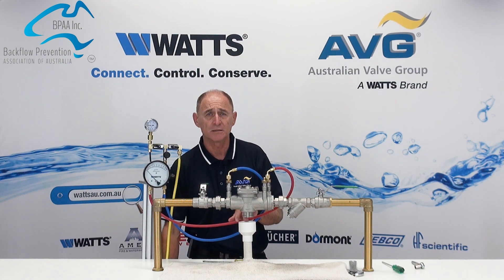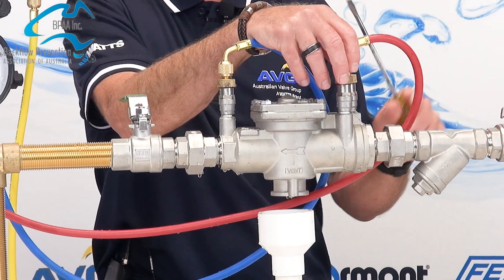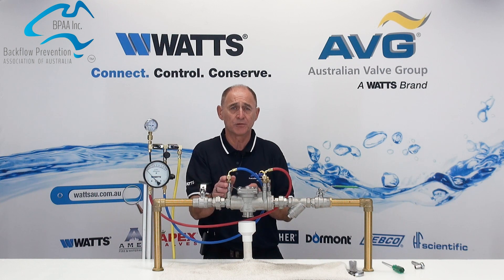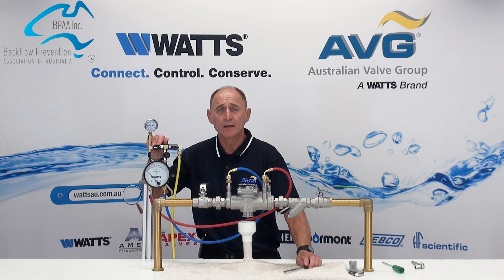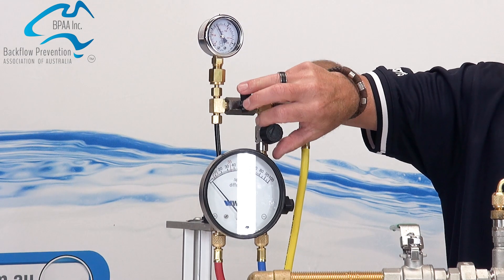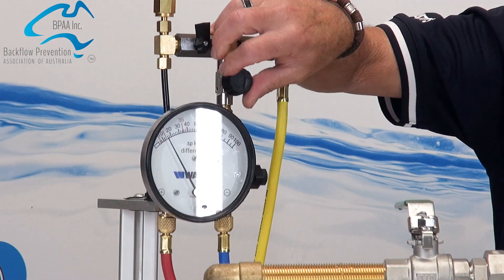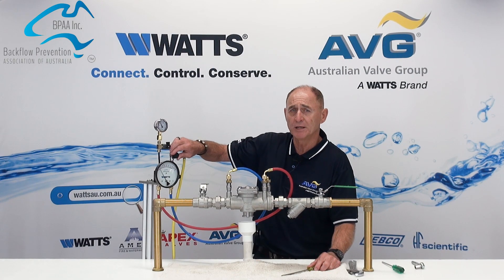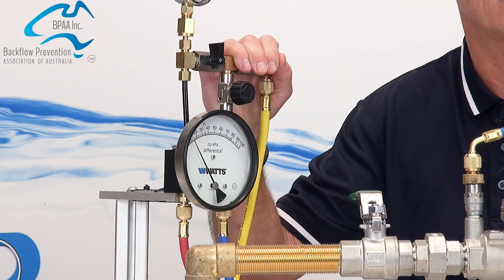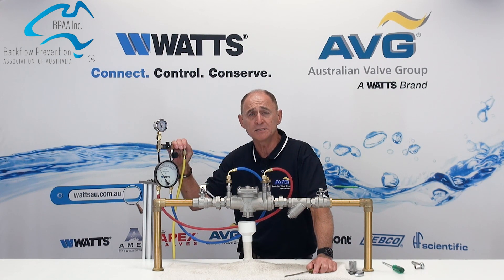We are now going to check the tightness of the number two check valve. Close test kit valve number one. Move the high pressure hose from test tap one and connect it to test tap number two. Open test taps number two and three. Slowly open test kit valve A and vent water through the vent hose. Close test kit valve A, then slowly open test kit valve B and slowly vent water through the vent hose. Close test kit valve B and record the reading on the differential pressure gauge. If the reading is below 7 kPa, then the second check has failed and shall be deemed faulty — the number two check valve shall either be replaced or repaired.